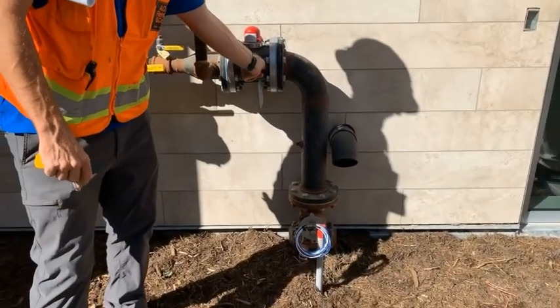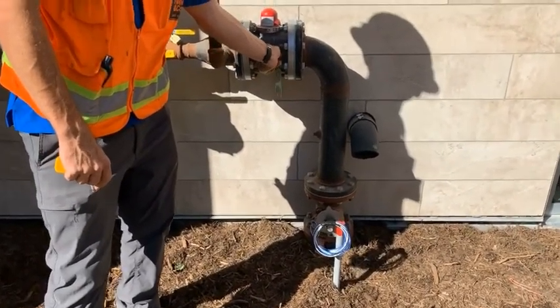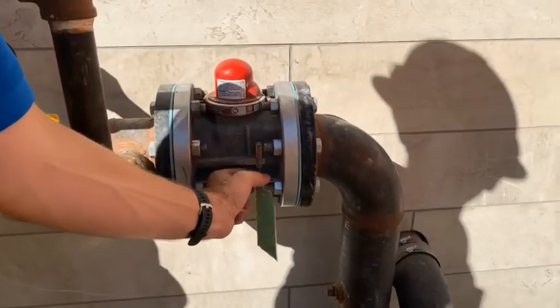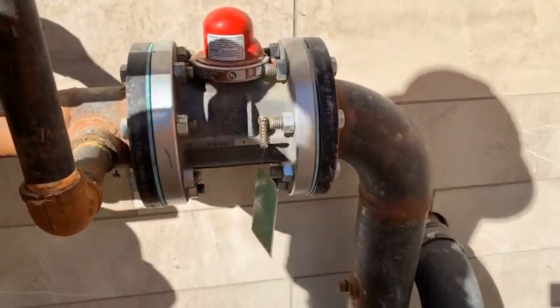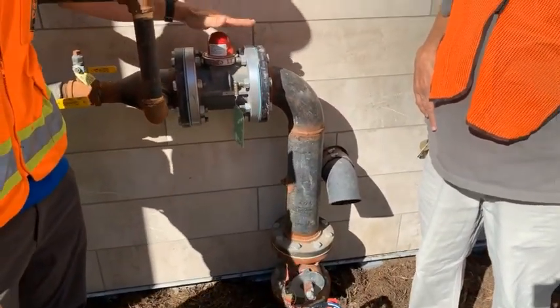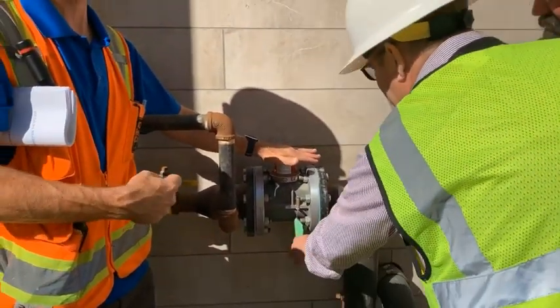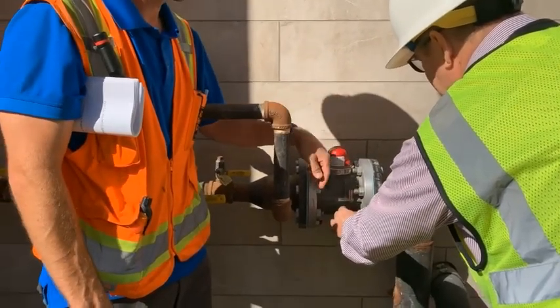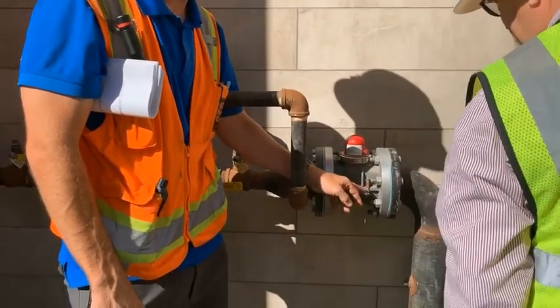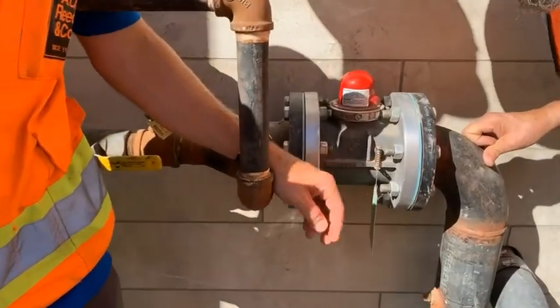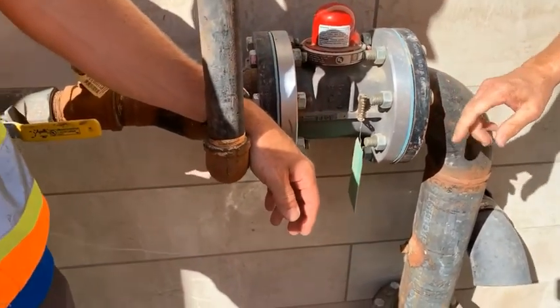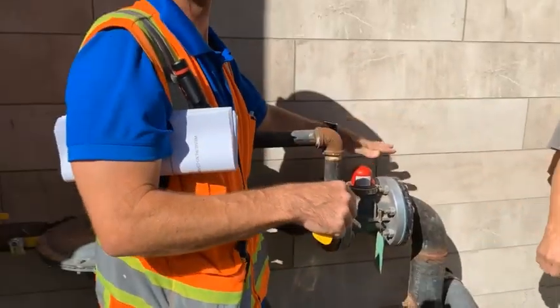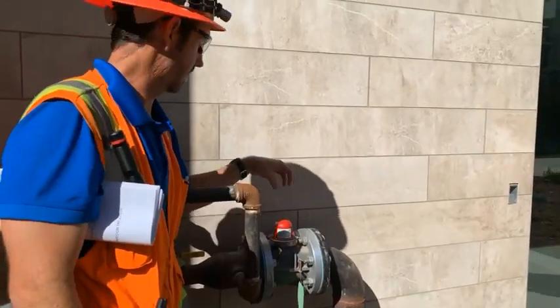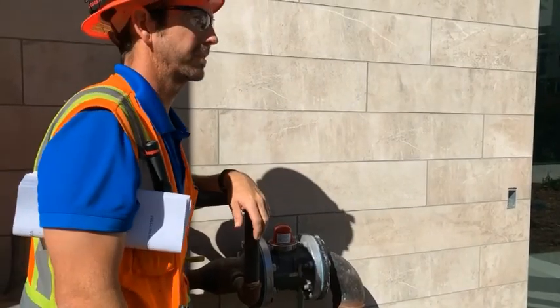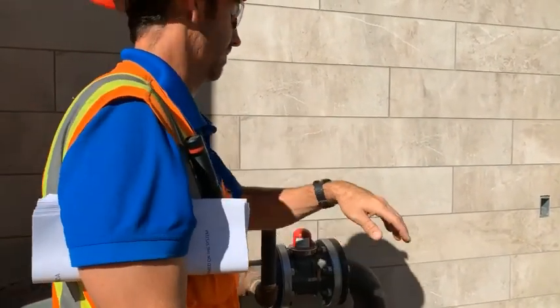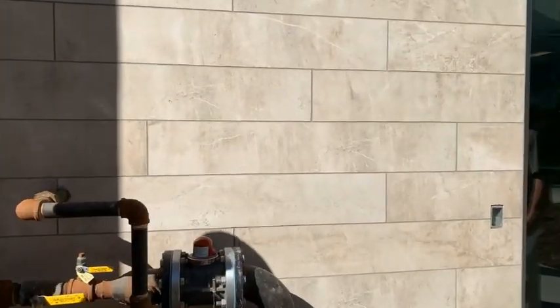And then if you ever have to take this apart, this little chain right here needs to be inside the circle, and the chain should be floating in the middle. That lets you see that the valve is level. This little tag stays on. And see how the ball's right in the middle? As long as it's right in the middle, we're good to go. Because if something changed and it's not in the middle, then it may not be level, and you might not be able to reseat the valve itself. It's like a big ball that sits on there. It just drops if something vibrates it off, and it closes the main valve.